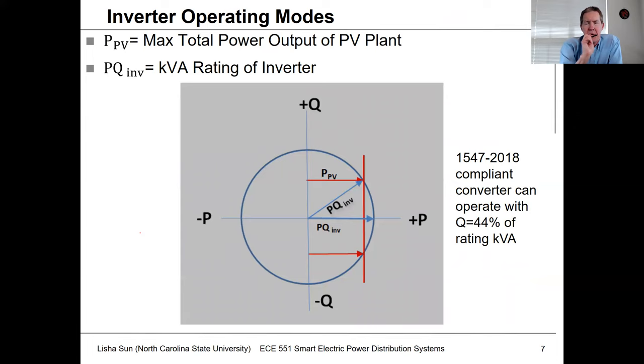As far as the model for the inverter, inverters are typically rated in terms of the amount of current they can handle. If you take the voltage times the current rating, that gives you a value in kVA or MVA.